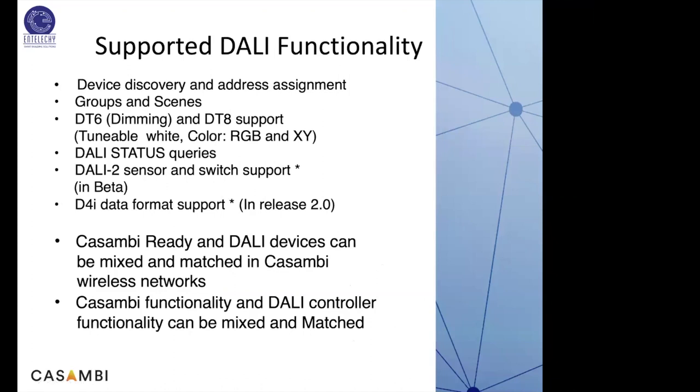Casambi supports almost all DALI functionality: device discovery and address assignment, groups and scenes using DALI DT6, DT8 support for tunable white, color RGB, and XY axis controls, DALI status queries, DALI 2 sensor/switch support, and D4i — the recent in-luminaire DALI standard. Casambi and DALI devices can be mixed and matched on the same wireless network, and Casambi and DALI control functionality can be mixed and matched together.